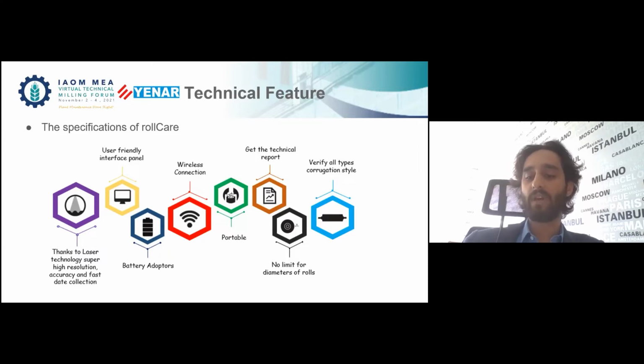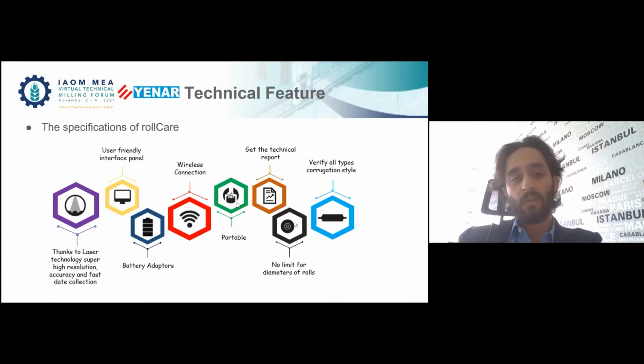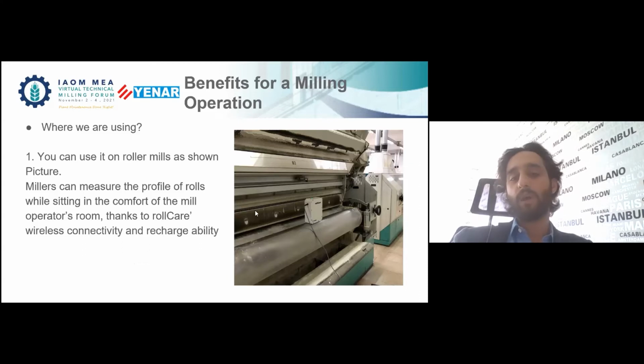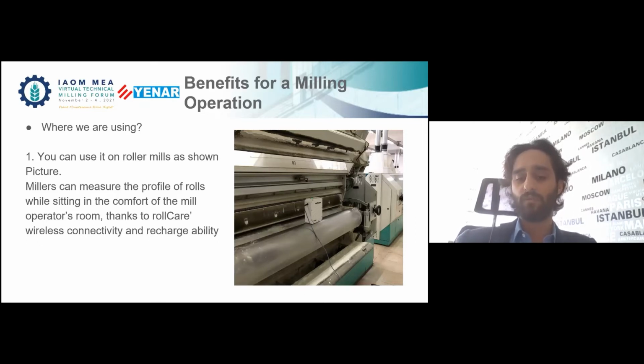And you can verify all types of flute styles in the rolls, especially fine cut, which means 14 flutes per centimeter on a 200 millimeter diameter roll, which is very difficult to measure. So you can use this device on fine cut rolls too. As you see in the attached photo, we use this device on the roller mills. As I told you, it's a very small piece, so on the roller mill you can use it like this.